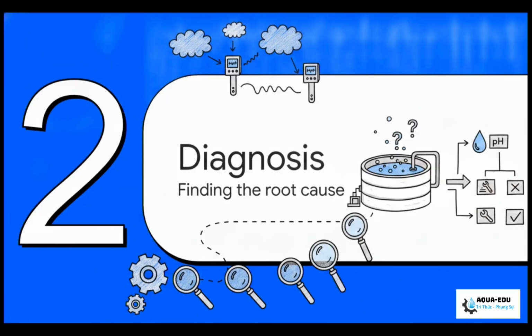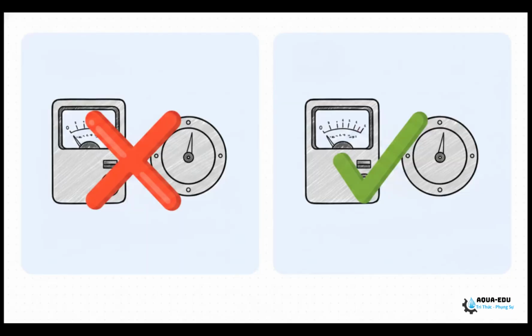Moving right along to Section 2, Root Cause Diagnosis. The second you see a red flag, your absolute first go-to action is to grab a well-calibrated handheld meter and take a fresh sample right there at the online sensor's location. Read them side by side. If the gap between your handheld and that SCADA screen is greater than 0.5, brothers, we have a confirmed sensor error, no question. Now, if the deviation is less than 0.2, it's probably just a normal fluctuation in the water source, so just keep an eye on it.